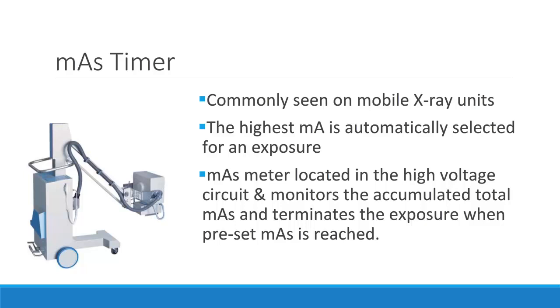The MAS timer is commonly utilized on mobile x-ray units. The highest safe MA is automatically selected for an exposure. An MAS meter in the high voltage circuit monitors the accumulated total MAS and terminates the exposure when the preset MAS is reached. This is why when an exposure is set on a mobile unit, the overall MAS is selected and the MA and time cannot be controlled by the radiographer individually.